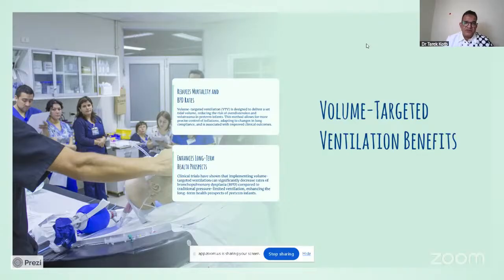Because you set the Pmax, once lung compliance improves, the pressure will go down on its own. So initially you need something like 25 pressure to achieve 5 ml per kilo, but after surfactant, after about one day on ventilator support, you don't need all these pressures. There is auto-weaning of the pressure. Now we need only 20 or 18 pressure to achieve the same tidal volume. So this is one of the recommendations for a ventilator protective strategy: to put the baby on volume targeted ventilation.